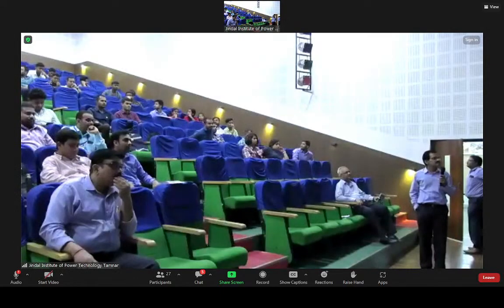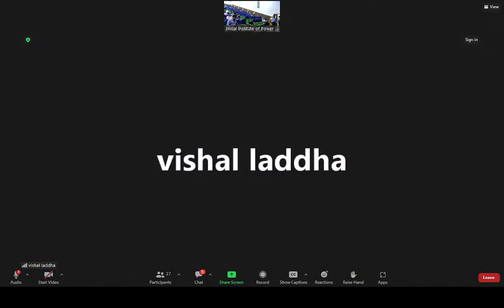Yeah, please speak. Sir, I want to share one more case study. Just 5 minutes ago at Jindal India Thermal Power, a problem came up. The unit was running at 600 megawatts, and suddenly one stop valve closed, an IV stop valve, in running condition. The operation people went to the field and suspected an ATT solenoid. They removed the solenoid and there was oil leakage. To attend to this leakage, they stopped the machine, and now they are trying to open the stop valve, but no stop valve is opening. All the stop valves are in closed condition.